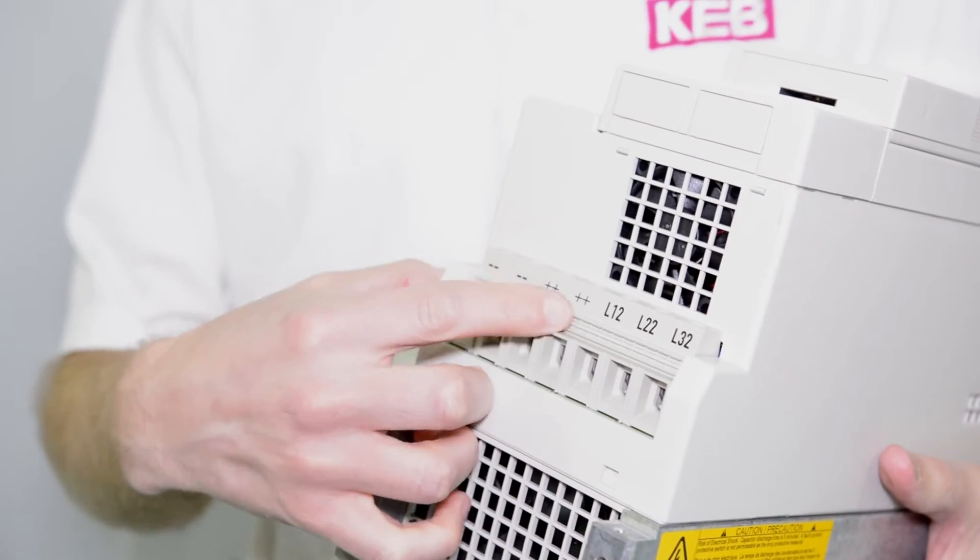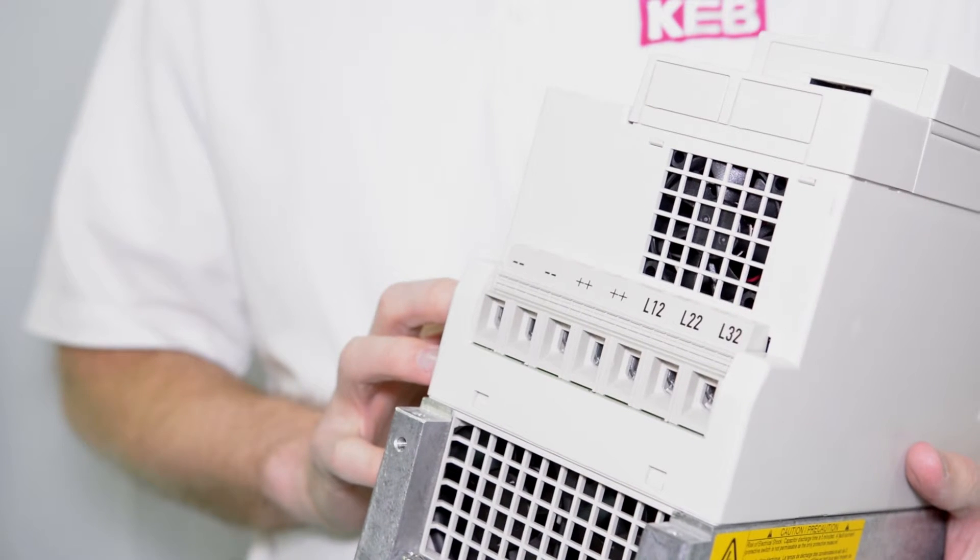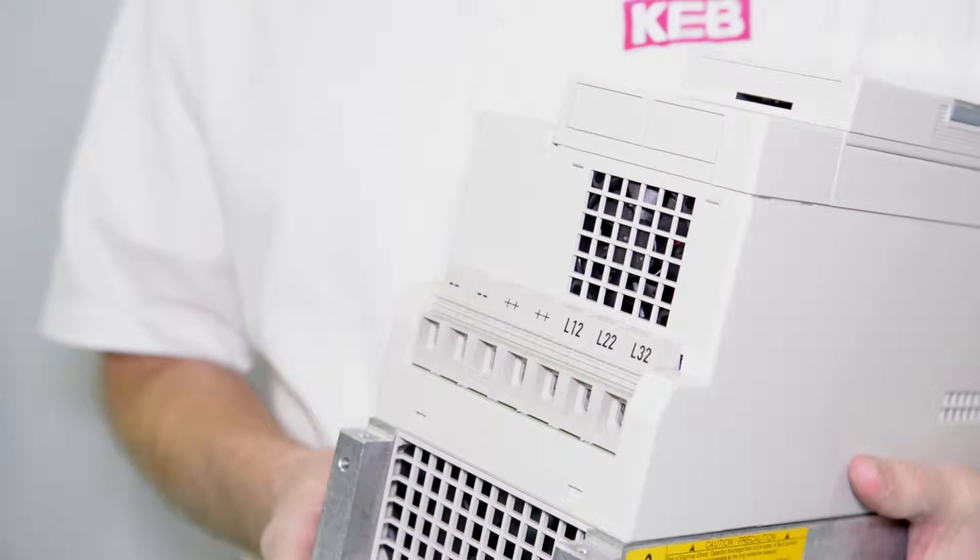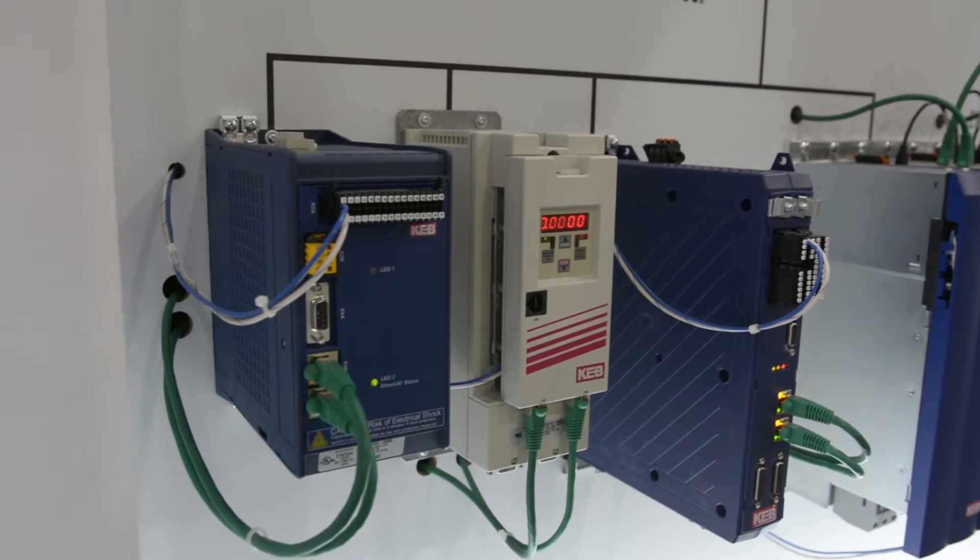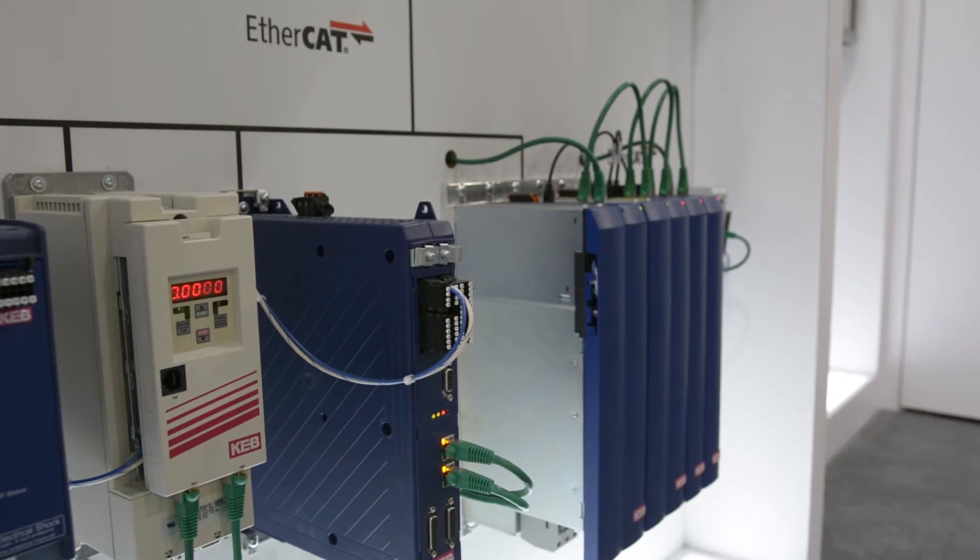You can see that there are multiple connections for the DC bus, so these units can be paralleled together if needed. This DC bus connection is where you connect the R6 Regen Unit to any VFD. It can be a KEB VFD or any third-party VFD that has the ability to bus tie.